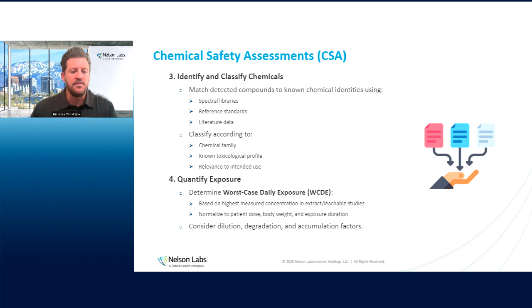From there, we'd move to quantifying exposure. We determine worst case daily exposure as an example, based on the highest measured concentration of those extractable leachables, and we normalize those to our patient doses and through that toxicological risk understanding. So in doing so, we're comparing the safety thresholds. So we're using toxicological databases. This process would be done by a well-qualified assessor to be able to help here and be able to identify potential toxicological risks. And then when specific data is unavailable, we are moving into other forms of risk mitigation, such as applying our TTC values or Cramer classifications, et cetera.